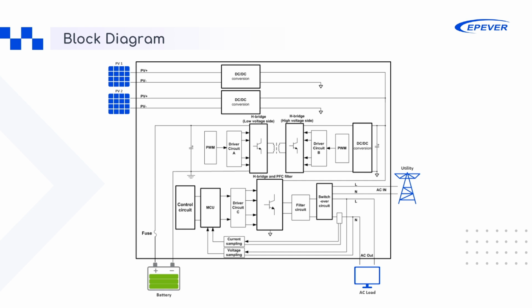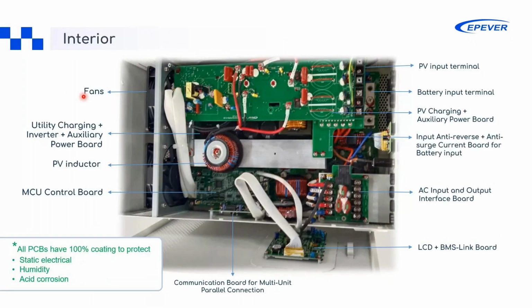So this is basically about the working principles of such a hybrid unit, and this one provides us an overview of the internal PCB. We start with the fans. This is a forced cooling system. We have fans over here, and it's important to dissipate the heat generated by internal components, and effective cooling is essential to prevent thermal stress on sensitive electronics. We will either lose lifespan of the instrument if it's working in a really hot environment, or the power will be degraded. That's what we don't want. That's why we have fans here.